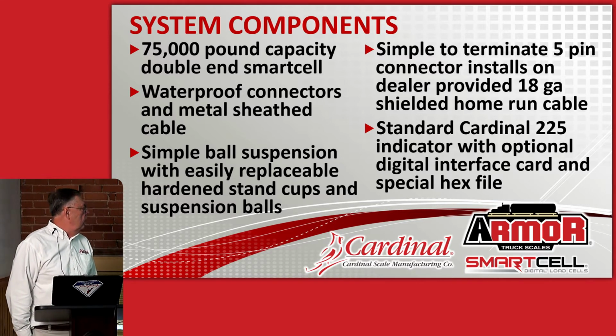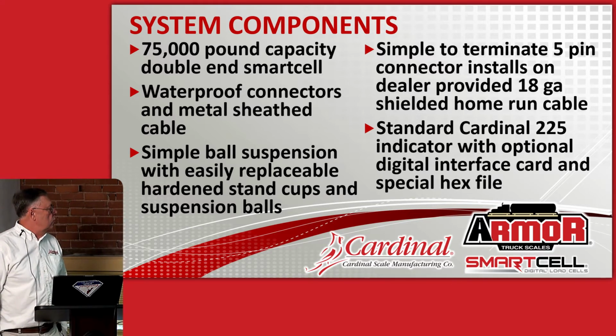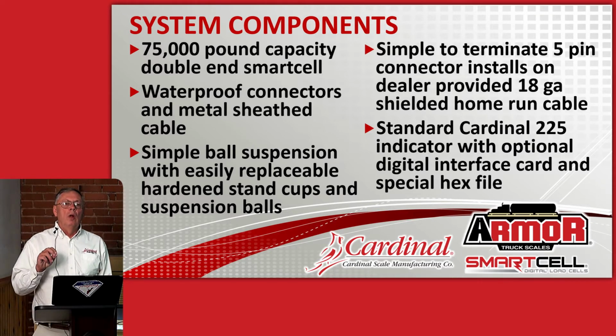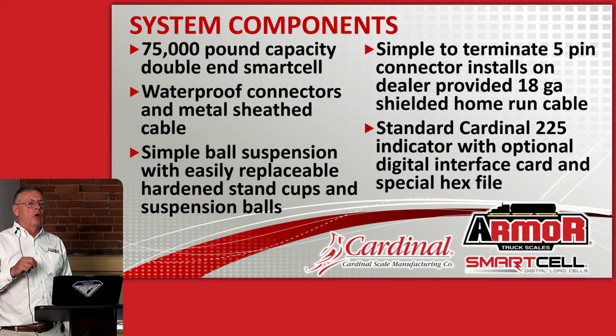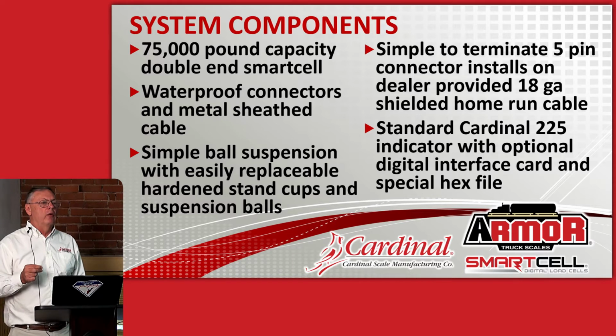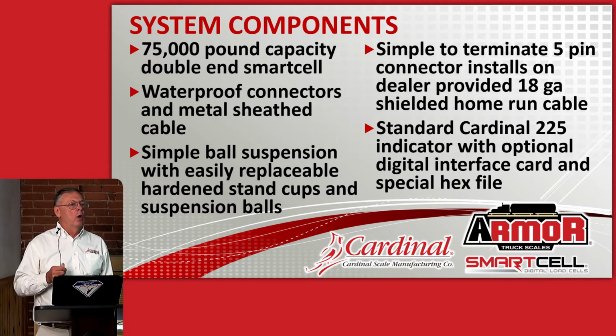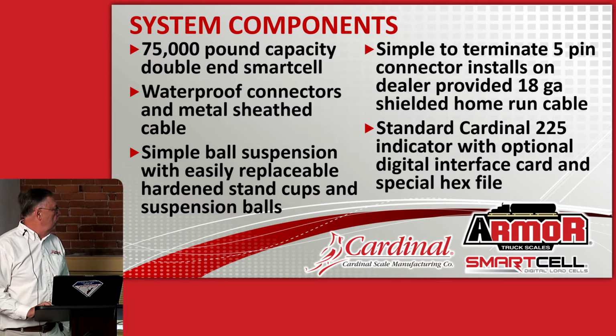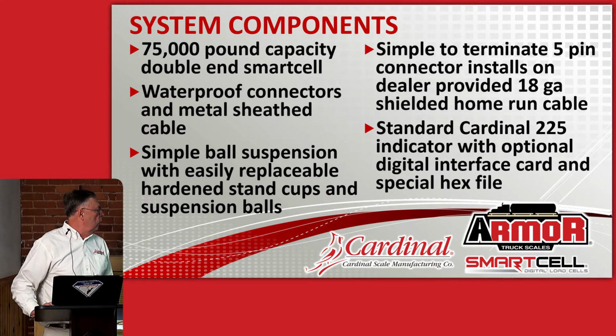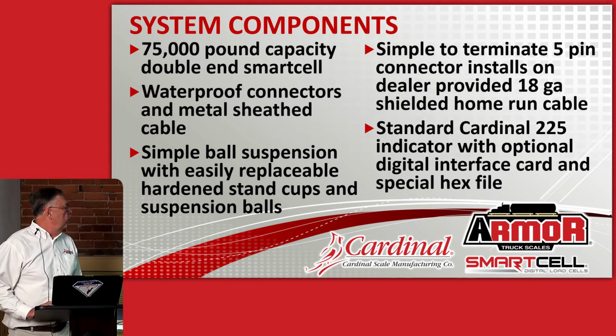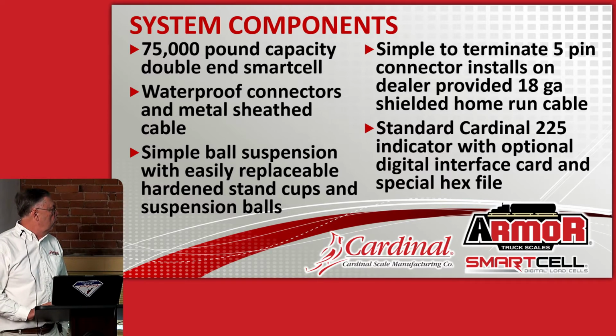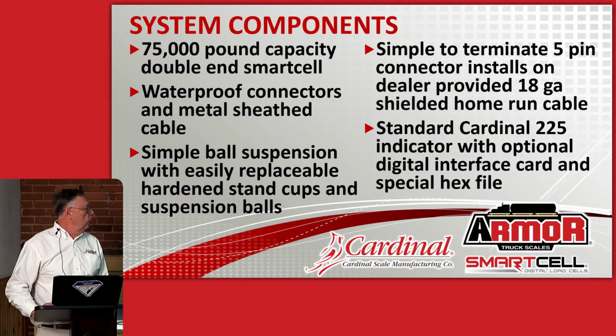In the field, the technician only has to terminate 5 wires in the indicator, and then there's a connector at the end of the home run cable he has to wire with 5 connections there, and that's pretty much all the wiring he has to do. Our standard Cardinal 225 indicator will run the system with an optional digital interface board and a special hex file that will be installed in the factory.